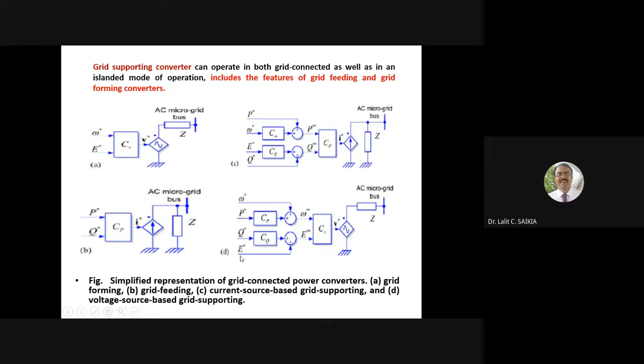So responsibility of these microgrid controllers: the main control variables in the microgrid are voltage, frequency, active power, reactive power. V or E, frequency F or omega, active power P, reactive power Q. These are the control variables. Thus, the microgrid controllers are responsible for voltage and frequency regulation under any operating condition, and P and Q control to achieve proper power sharing under grid connected as well as islanded mode of operation. That is, first responsibility is to control the voltage and frequency, number one, in any operating condition. Number two, P and Q control to achieve proper power sharing under grid connected as well as islanded mode. A seamless transition from grid connected to islanded mode and vice versa.